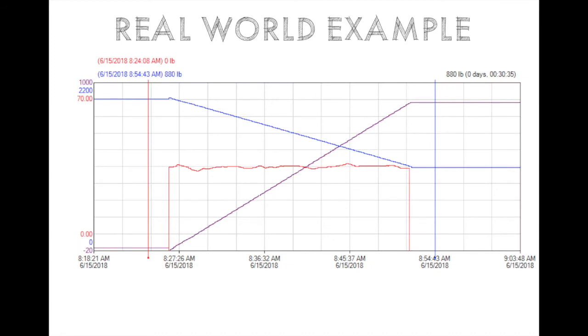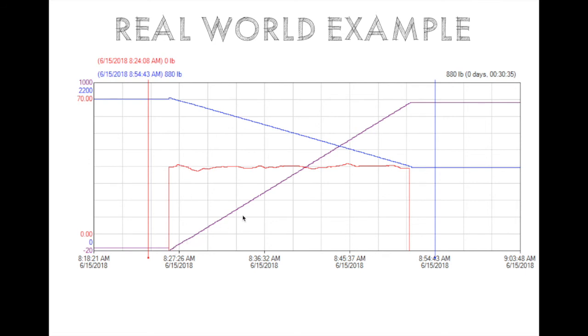So all the while this is happening, there is a totalized amount of powder fed that the PLC is doing, which is this purple. And this is required because we need to know exactly how much we put in. So essentially, it's integrating the area under the curve of the flow rate, which is the red. So over the course of this batch, the totalized amount of powder that goes through ends up being about 880 pounds, shown here as this 880 value, which is the value of the totalized amount, the purple, at this blue vertical cursor.